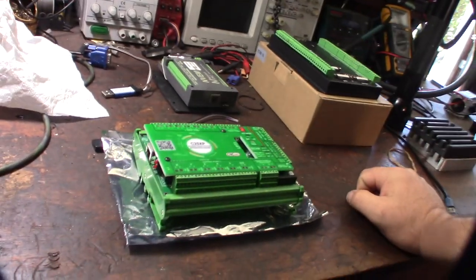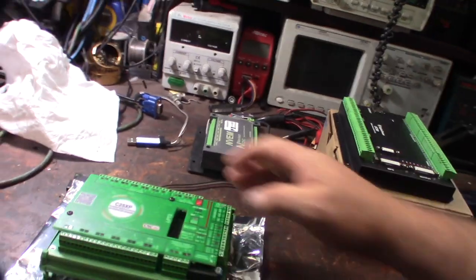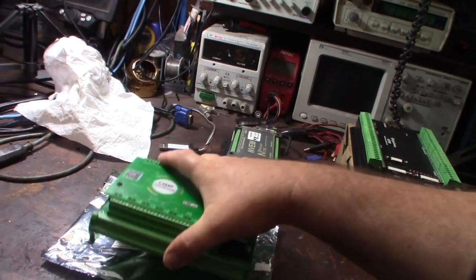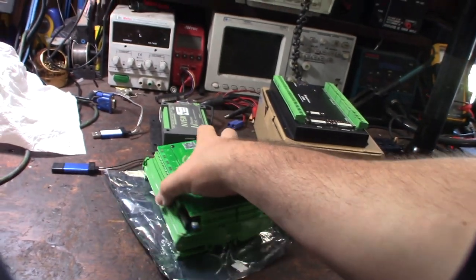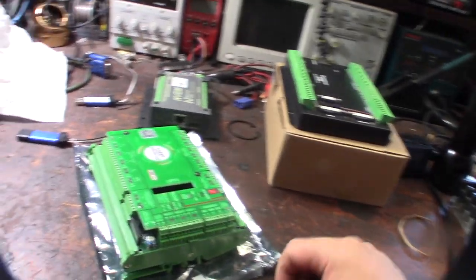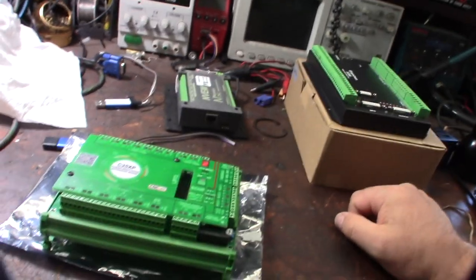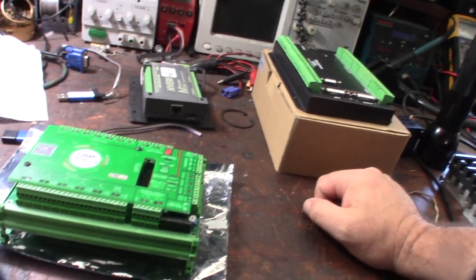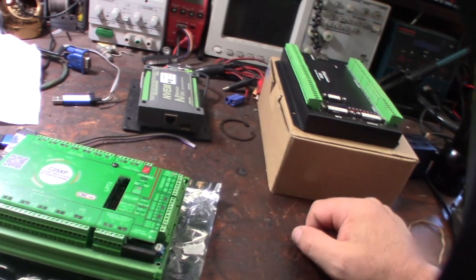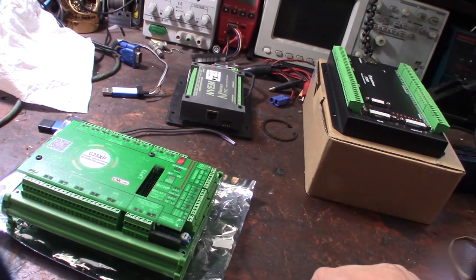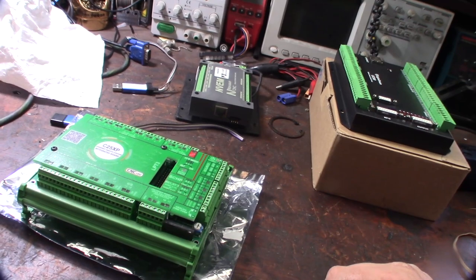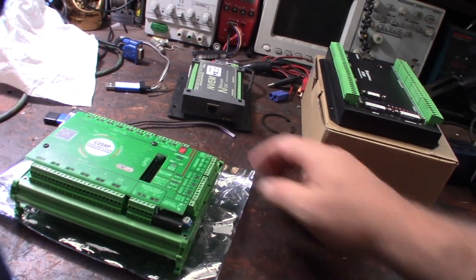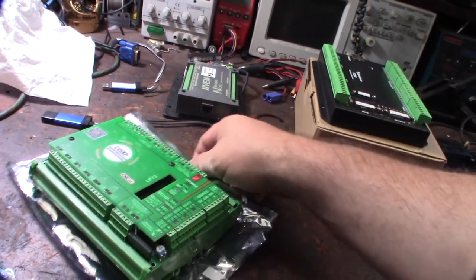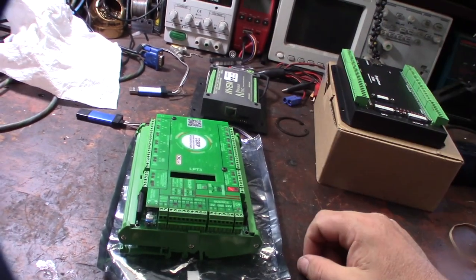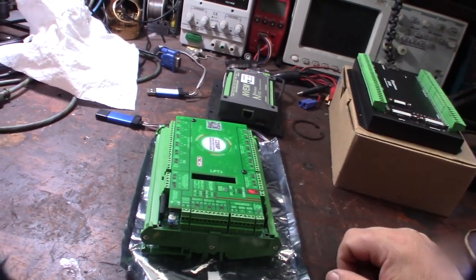I guess I could have 3D printed one and designed one, but I like how nice and compact the thing is. So this is your analog trim pot. Sometimes when you hook up a VFD to these devices, it can pull the voltage down. Normally this would be 10 volt, but when you connect it to a VFD, it might pull it down a little bit, like half a volt. So you can go back with this little trim pot and turn the voltage back up to get in that 10 volt range.